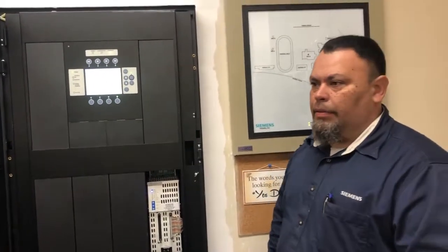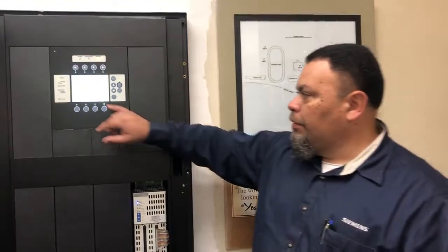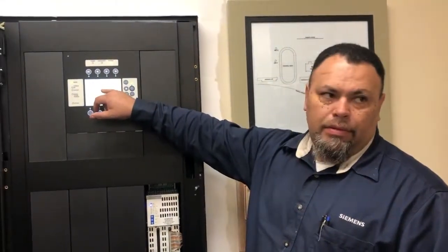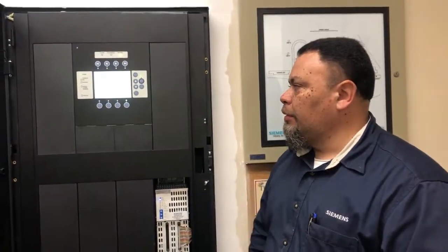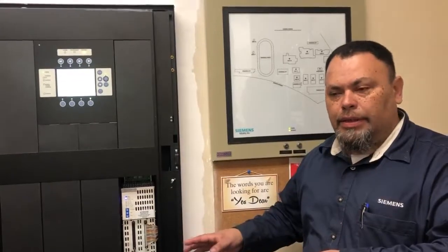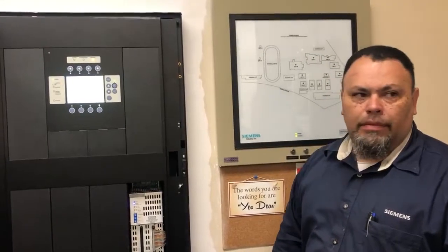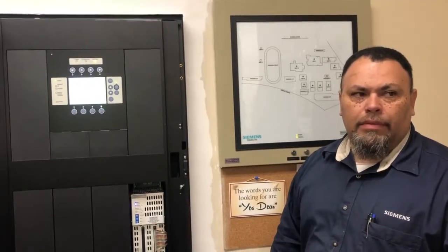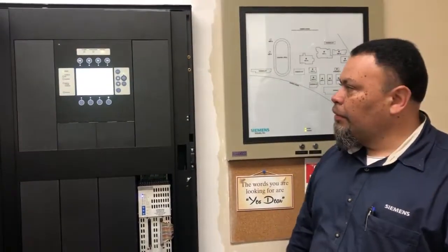I can tell you that when I was here the last couple of weeks working on this, the only trouble that was showing up was this D2 smoke detector. That was there before. That one has happened already two times. Again, I don't know the history on this panel, how long it's been in place. But it would definitely be a service call to our service department. Yeah, that heat detector, I have it in the emails. It was activated, and we brought it to their attention.